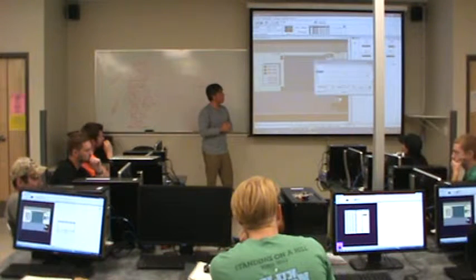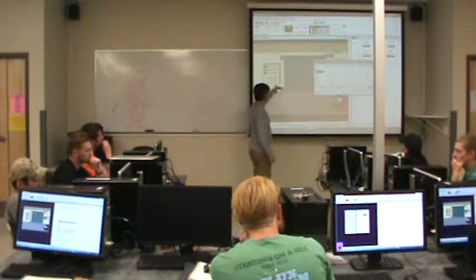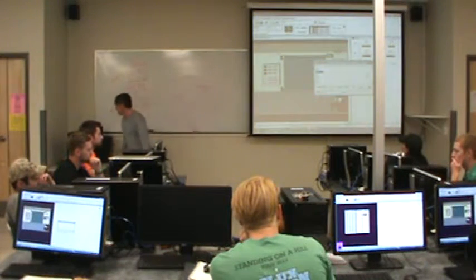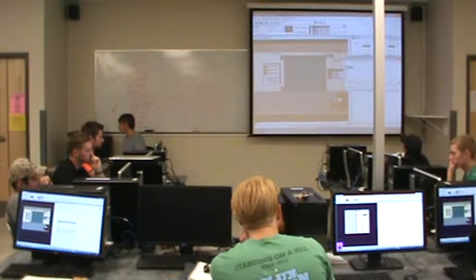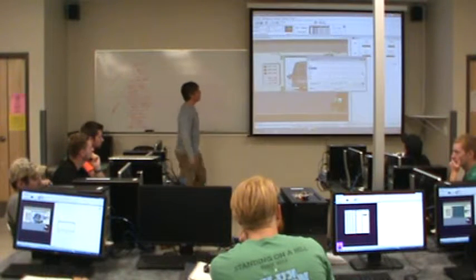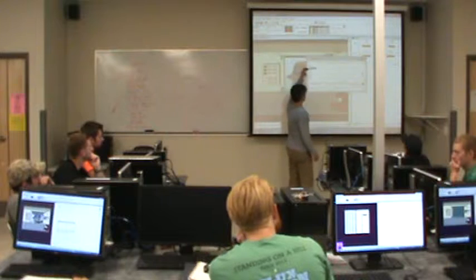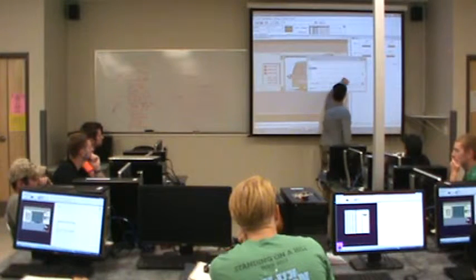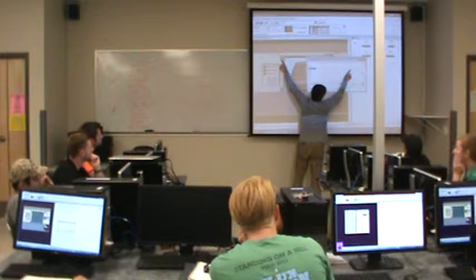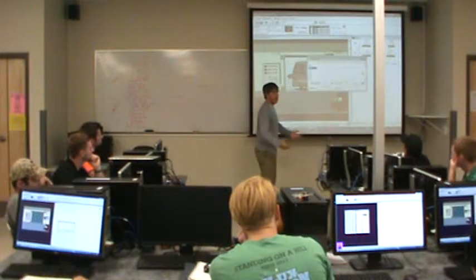Make sense? So if I raise the door, what I would expect is to see input 3 and input 4 turn off. Let's find out if that's true. I have to be really careful because I want to clear this limit switch without burning up the motor. So let's open and got it. Sure enough, the 2 bits on input word 1 of interest, bit 3 and bit 4, which represent both limit switches, bit 3 being the upper limit switch and bit 4 being the lower limit switch, sure enough, they both turned off.